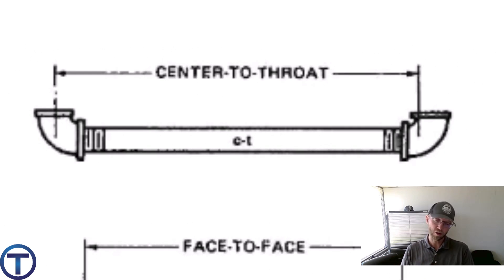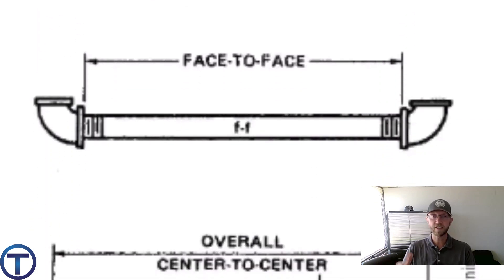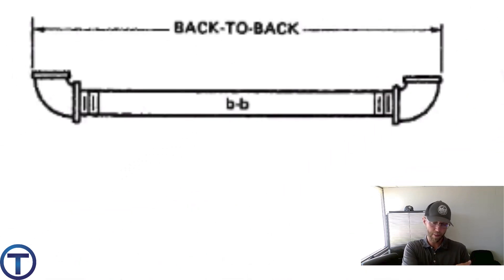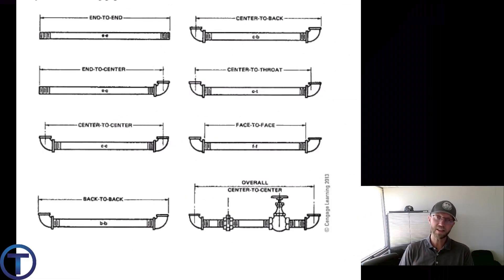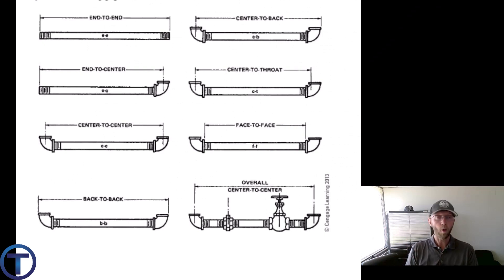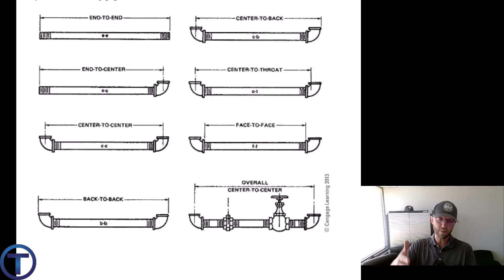Other measurement references include center-to-throat, where the throat is the inside lip of the open fitting. You might also measure face-to-face, which is where the fittings stop and the pipe extends beyond, or back-to-back, pulling from one back side to another. In any of these situations, be aware of what you need to subtract or add. With face-to-face, for instance, you add back some length so the pipe is long enough to extend into the fittings.